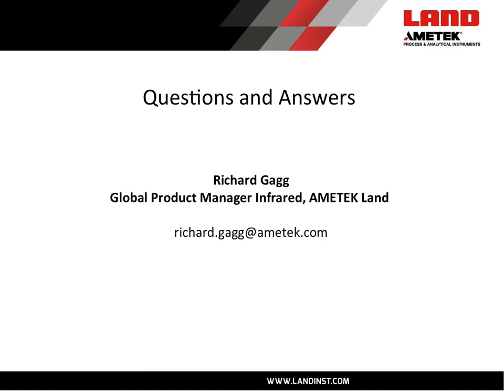Okay Richard, thank you very much for that great presentation. We do have time for a few questions. Here's your first question: how do I know the emissivity of my steel forging? The easiest way is to look up the emissivity value in the tables at the back of the user guide for that pyrometer. If you don't have that available and it's possible, you could also touch the item with a thermocouple and adjust the emissivity dial on the instrument until the two readings match.